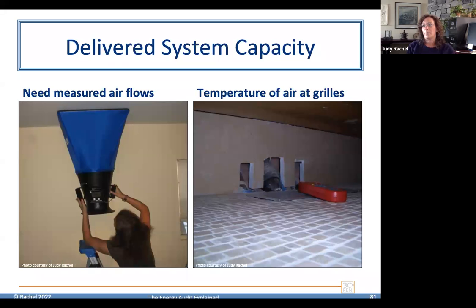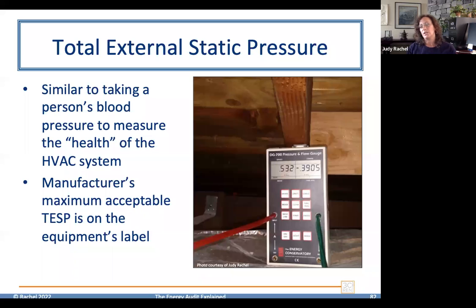So delivered system capacity is a test that tells us the capacity of the system that you're testing. If I have a 5-ton system on a house and I want to find out, is it delivering 5 tons of capacity to the house, this is the test that would be done. That test means I need to measure all the airflows of the supplies in the house as well as the returns, and I need to get the temperature of air at each of the grills. From that, there's a formula that's used to calculate how much capacity is actually being delivered to the house.